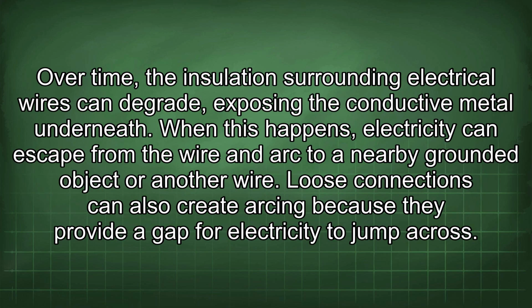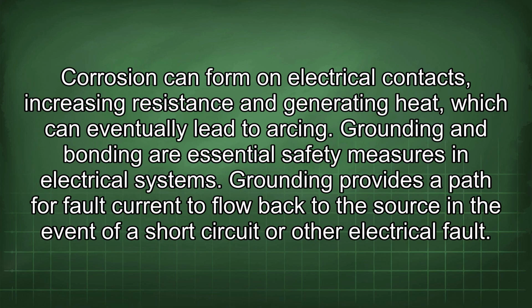Over time, the insulation surrounding electrical wires can degrade, exposing the conductive metal underneath. When this happens, electricity can escape from the wire and arc to a nearby grounded object or another wire. Loose connections can also create arcing because they provide a gap for electricity to jump across. Corrosion can form on electrical contacts, increasing resistance and generating heat, which can eventually lead to arcing.